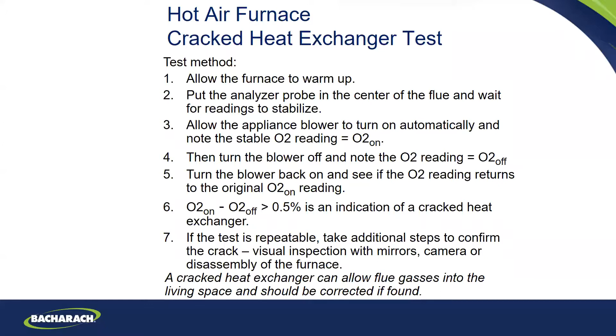Okay, see, the problem with a crack is if you have a crack in here, 9 times out of 10, air goes from the plenum, the air side, through that crack into the heat exchanger. So it's not really bothering you. But it's that 10% of the time we're worried about it going out, okay, that you can get CO into your house. So we're going to turn this on, and it only has this differential in pressure when the blower's on.